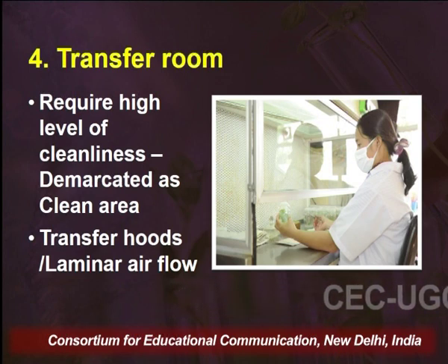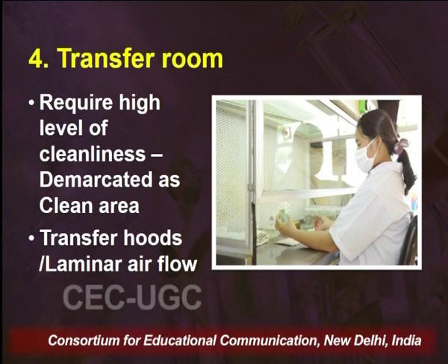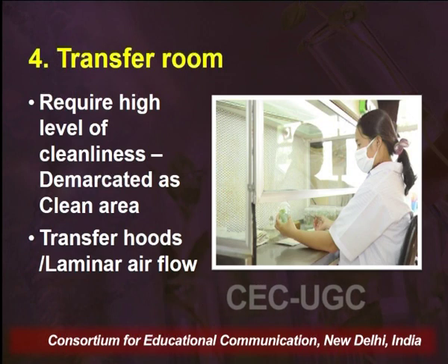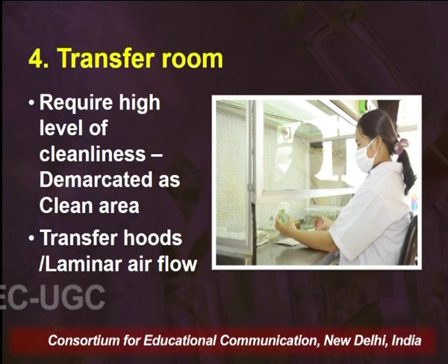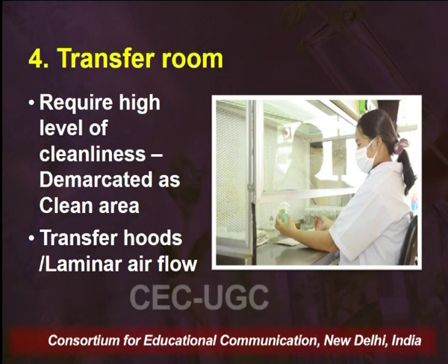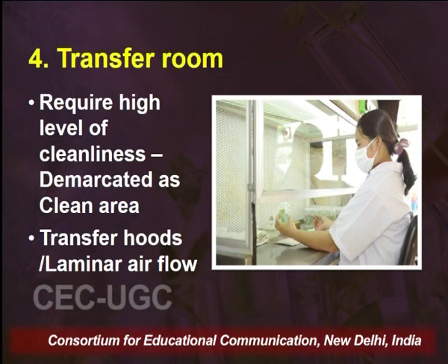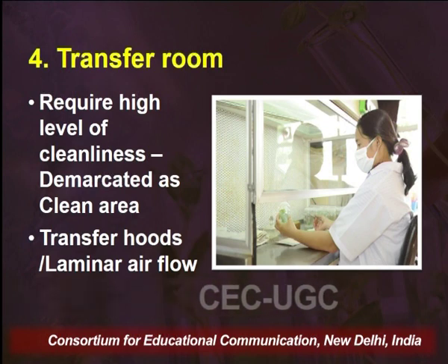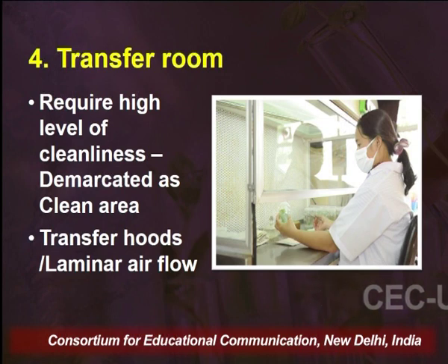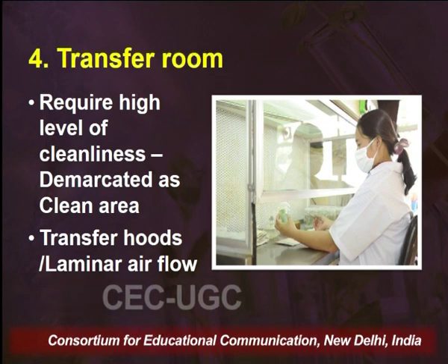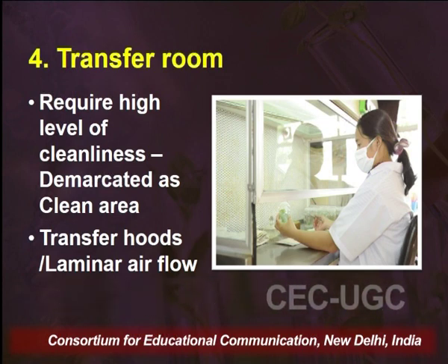Once you have prepared the media, it is then shifted into the transfer room, wherein the explant material is shifted onto the culture media. Now this transfer room requires a high degree of cleanliness in order to avoid any kind of contamination. I have discussed that such areas should be demarcated as a clean area in this complex. Now these transfer rooms should always be equipped with transfer hoods which can be easily sterilized. Preferably these transfer hoods should have laminar flow fitted with HEPA filters.